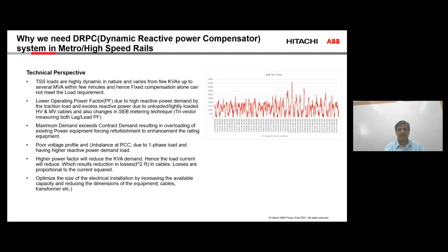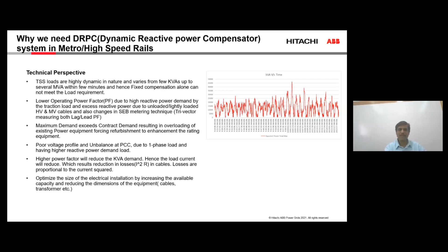And when we put in a compensator and correct these things, a higher power factor will immediately reduce the kVA demand, reduce the load current, and reduce the I squared R losses, and all of these have positive benefits for rail. And not only does it give a direct benefit like this, there is an indirect benefit: while designing a new station, if we have a compensator factored in, we can optimize the size of the electrical installation and not oversize it, given these power issues.